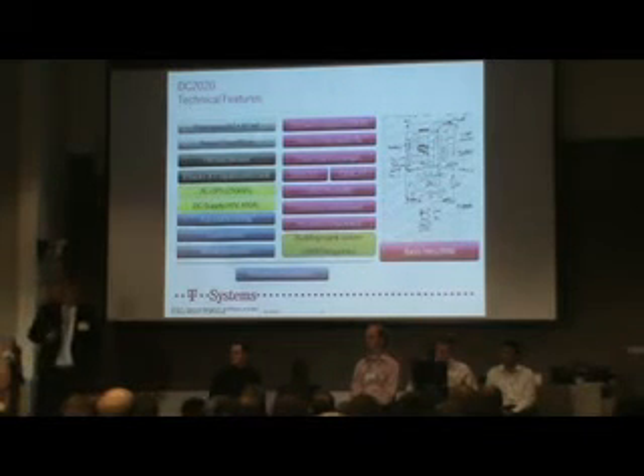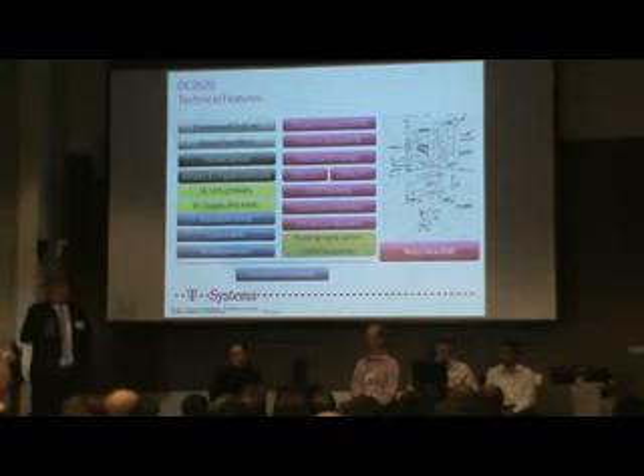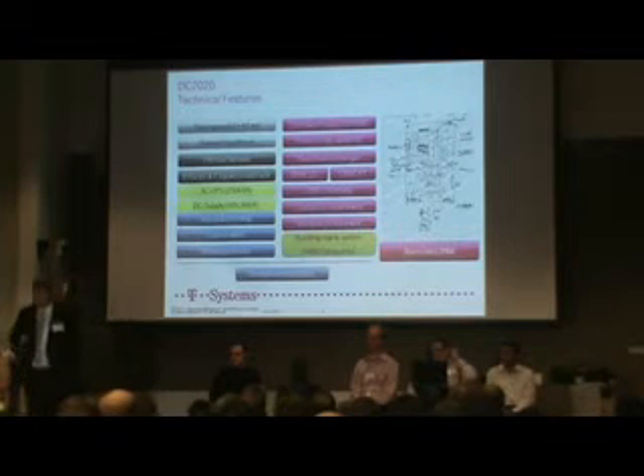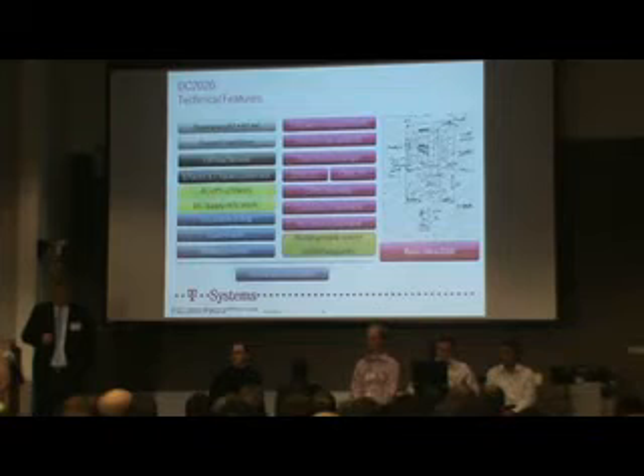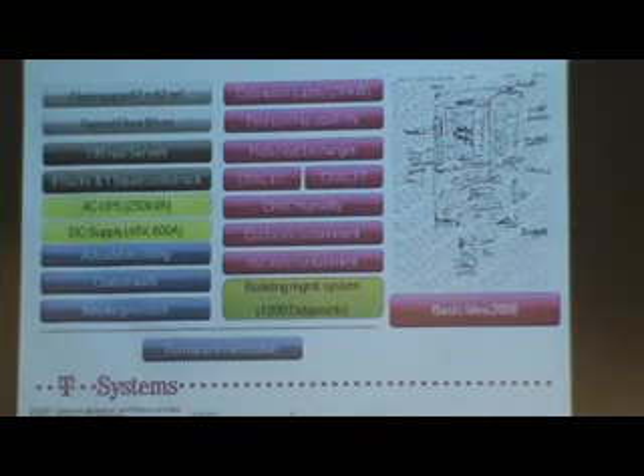The technical features of the data center are all a normal data center must have. It's on a floor space of approximately 70 square meters, and only to give some specials here, we have an adjustable ceiling, so we can move the ceiling from 2.5 meters up to 3.7 meters above the raised floor to check the influence of the room height, the room volume, on air conditioning. And we have a smoke generator for visualizing the effects of airflow on energy efficiency. And one of the highlights is our building management system and our measuring system, and we have more than 1,800 data points correlated to these 70 square meters.